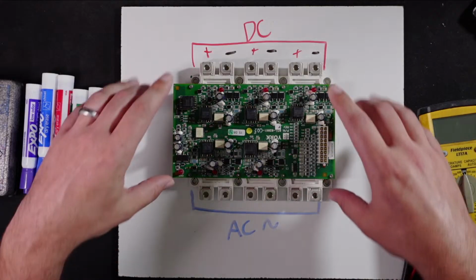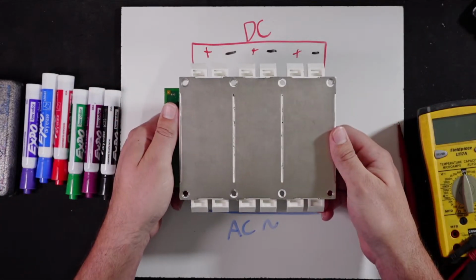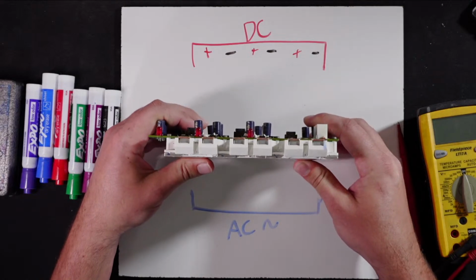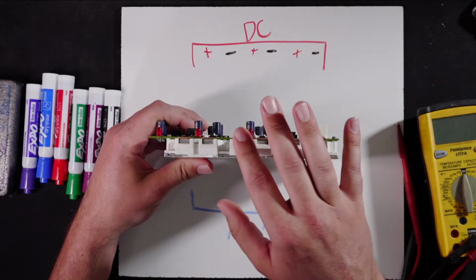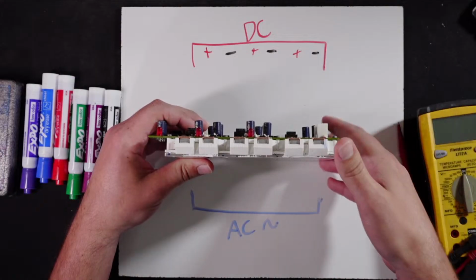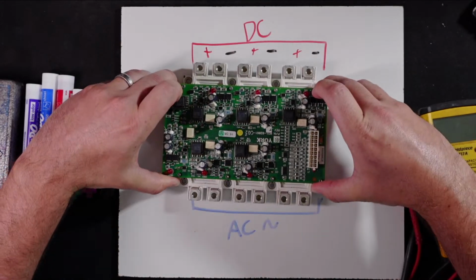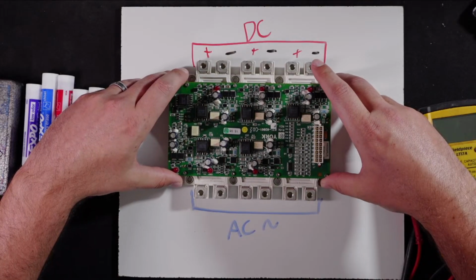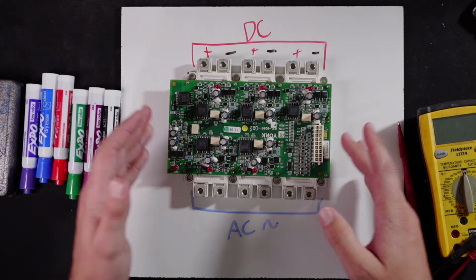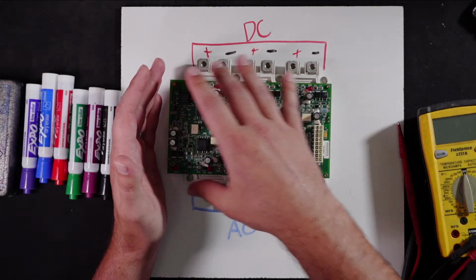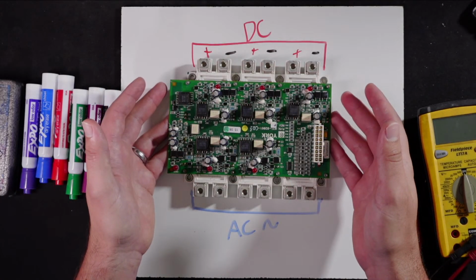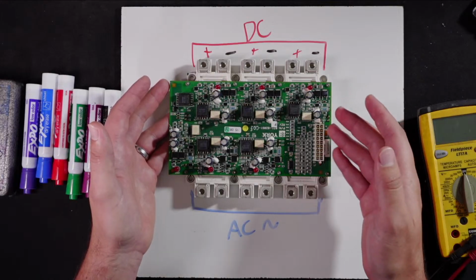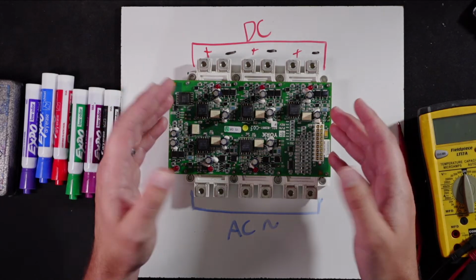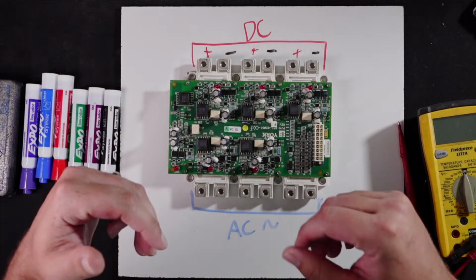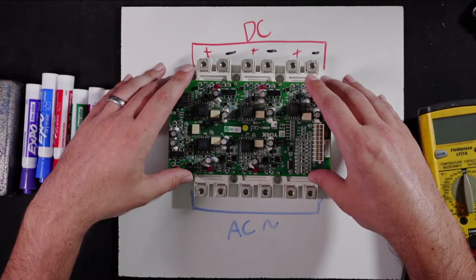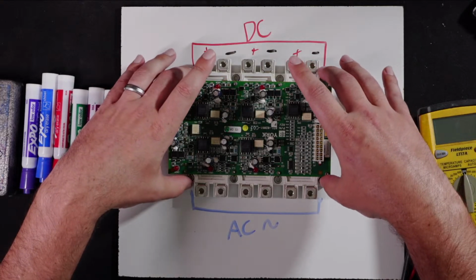So in my experience, one of the more common failures I'll see is heat related, where the cooling system, which is what this is down here, these are plates. When these are in operation, they generate a lot of heat. That heat is just waste energy that is natural to using solid state components. We haven't developed technology to avoid that yet. It just is what it is. So we have to reject that heat somewhere. This particular one would have used a liquid cooling system. Some systems will use an air-cooled system to cool a heat sink. Those variations will vary.